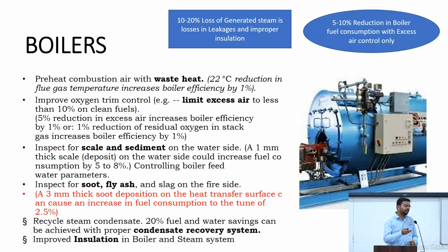It generates CO. And if we supply excess air, some excess oxygen will remain in the flue gas, which increases the losses of the boiler. So we need to maintain an optimum oxygen level. We check this oxygen level in every boiler analysis, as well as scale formation, sediments, and feed water quality. There is also fly ash and soot formation on the boiler coils. We need to check this, because 3 mm thick soot can increase our energy consumption by 2.5%. During boiler analysis we check all these things, so we get a glimpse of the normal ECMs that the industry can implement.